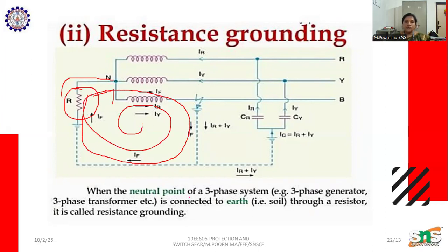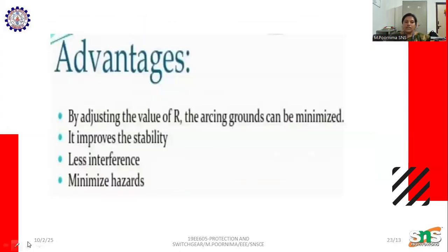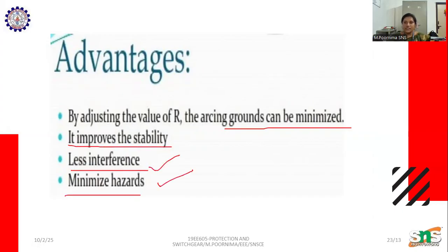So when the neutral point of a three-phase system, such as a three-phase generator or three-phase transformer, is connected to the earth through a resistor, it is called resistance grounding. What are the advantages of this grounding? By adjusting the value of R, the ground fault current can be minimized. It improves stability, reduces interference and minimizes hazards. So these are the main advantages.